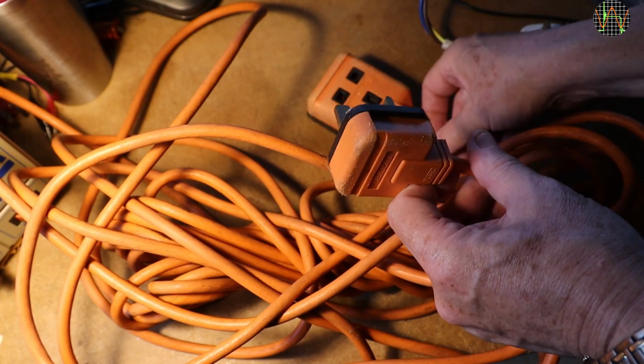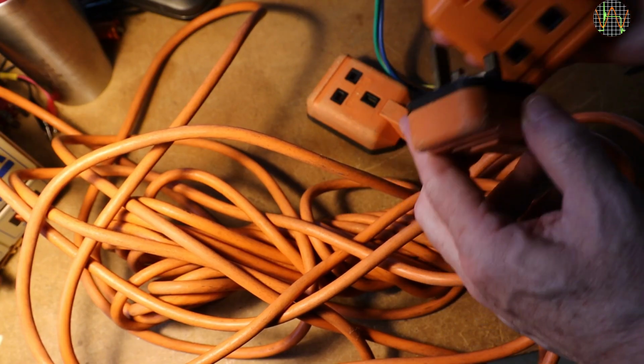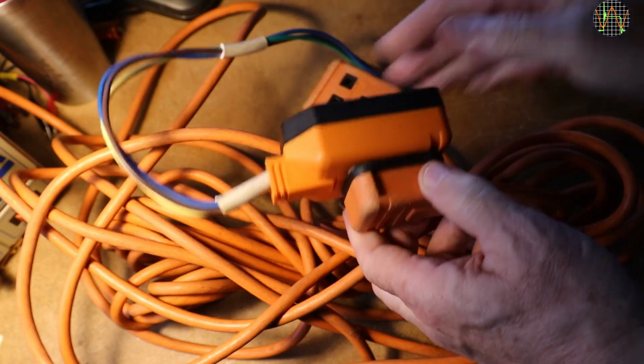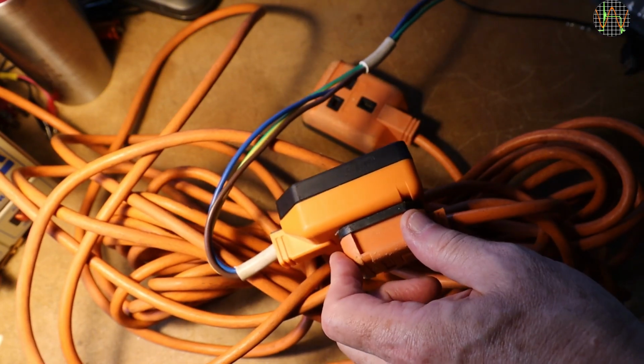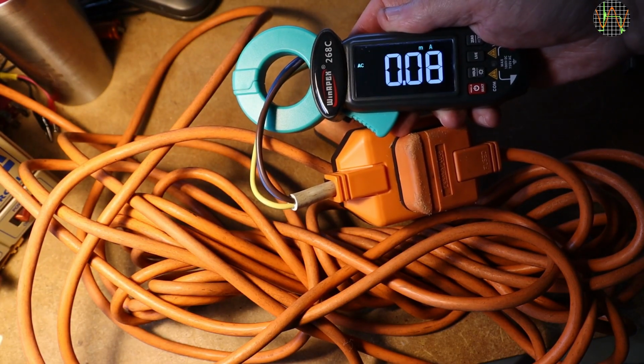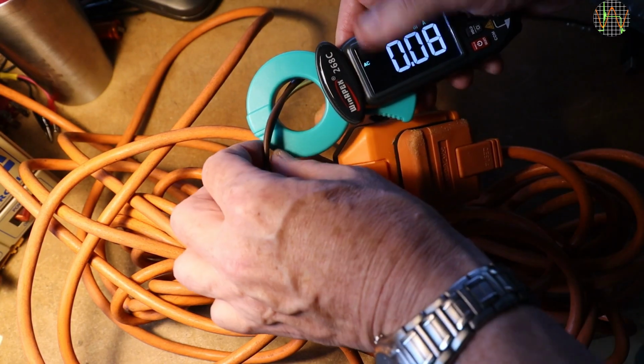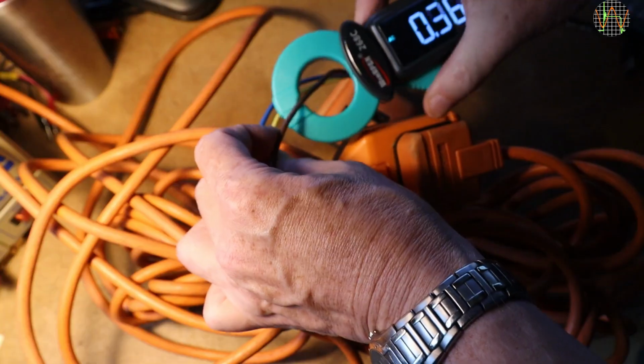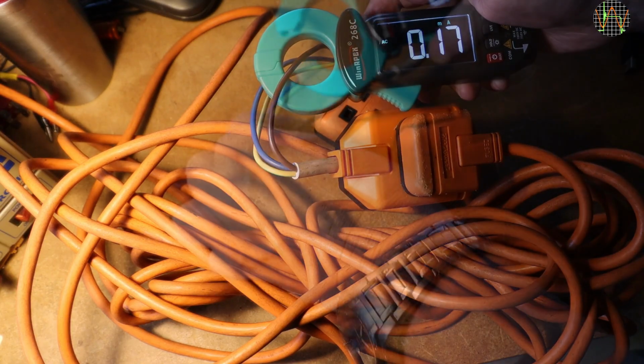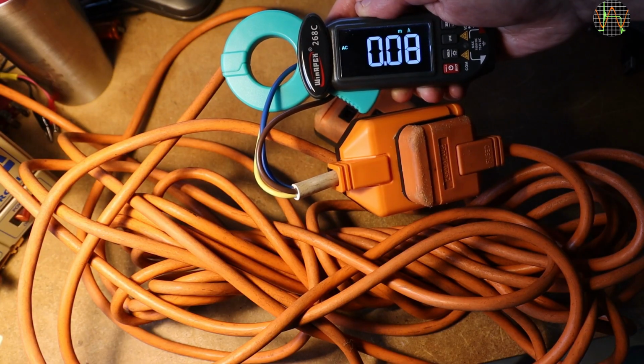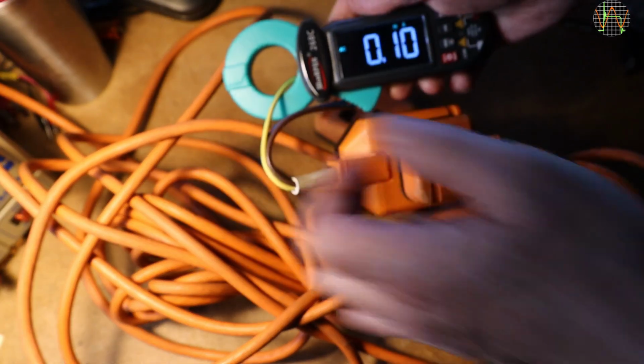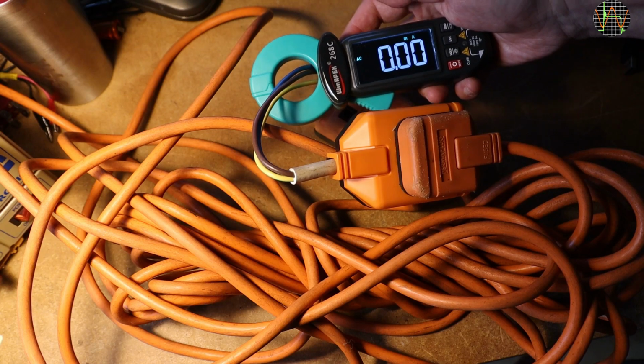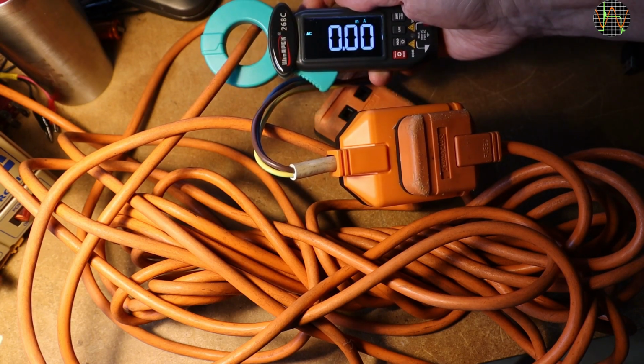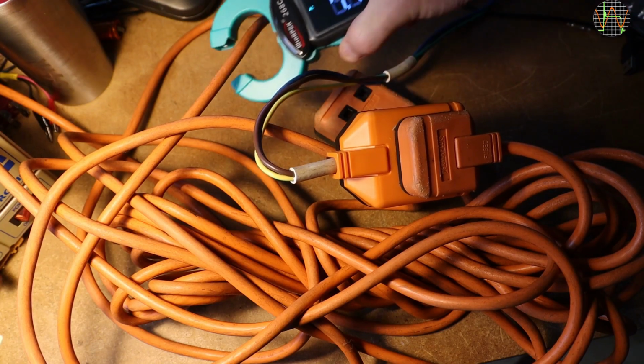Here's another interesting case. A simple 20-meter extension lead. Let's plug it into the rig and power it on. With a clamp on L and N, there's an imbalance of already 0.08 milliamps, and there is nothing connected to this extension cable. The current on L is 0.16 milliamps. The blue N wire has only 0.08, and the earth wire carries the rest, also 0.08 milliamps. Measuring all 3 conductors together reads 0 because the current in L is compensated by the currents in N and E. And of course, you get the same by putting the cable itself into the clamp.